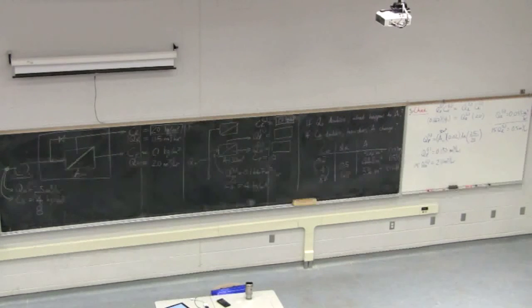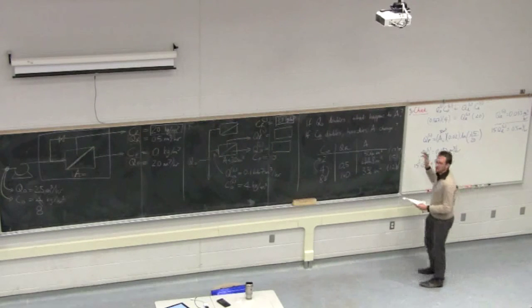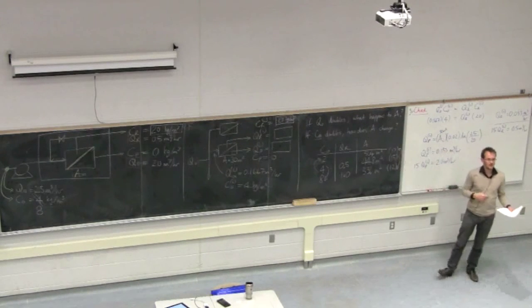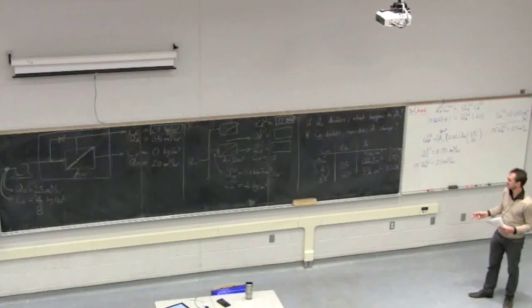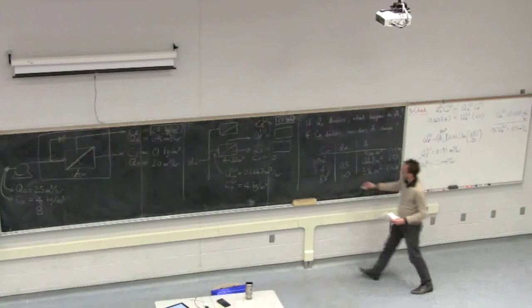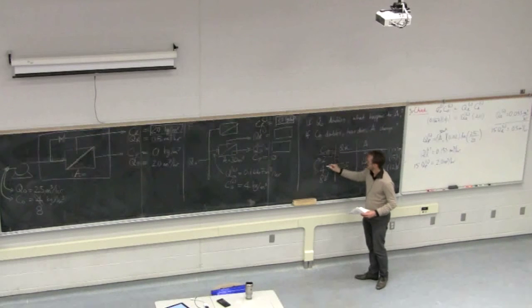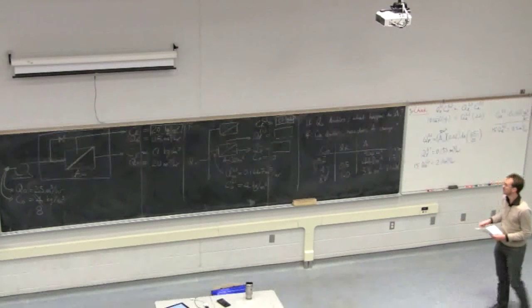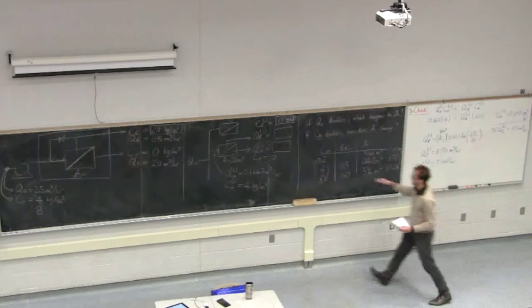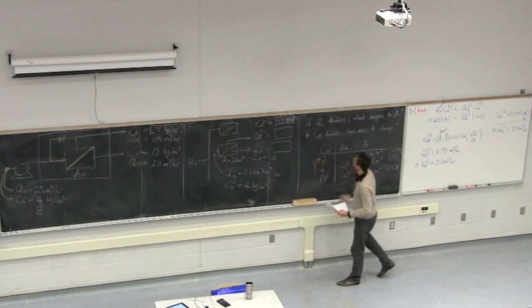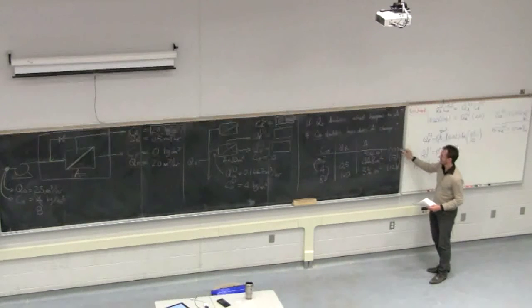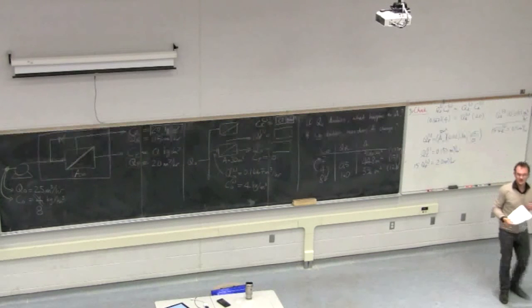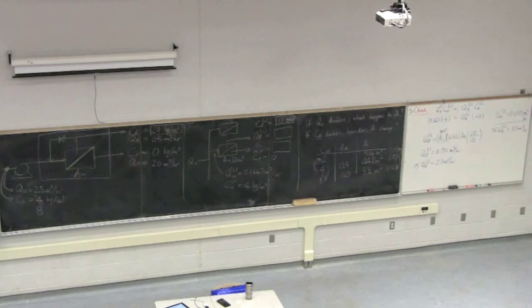So the thinking that I want you to take from this is, as I always emphasize in this class, there's always a trade-off between operating costs and capital costs. Changing C naught is something that you can do quite easily. You can dilute your feed with water. Okay, so if you're going from 4 down to 2, that's an easy process. But it's going to cost you a little bit more capital. You're going to have to buy those two extra membranes. But what's interesting is the sensitivity. The area isn't quite as sensitive to changes in the feed concentration. That's a good engineering insight.